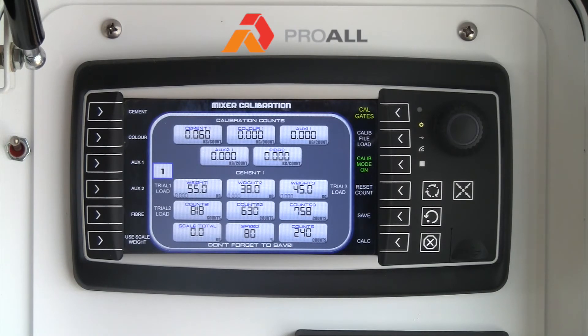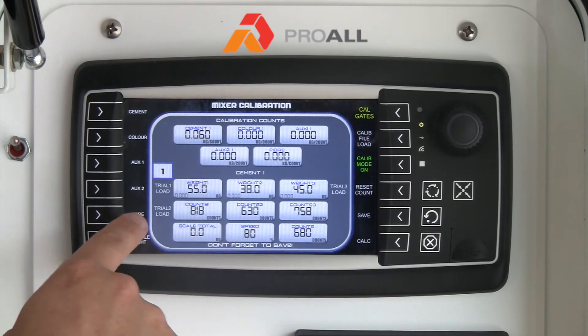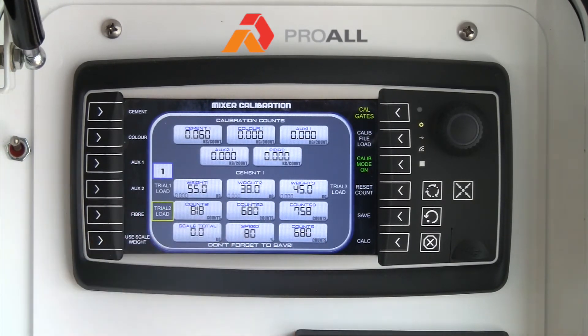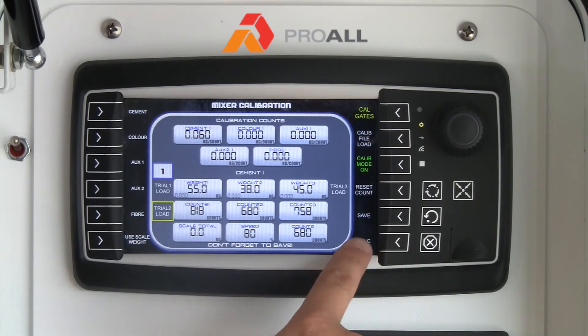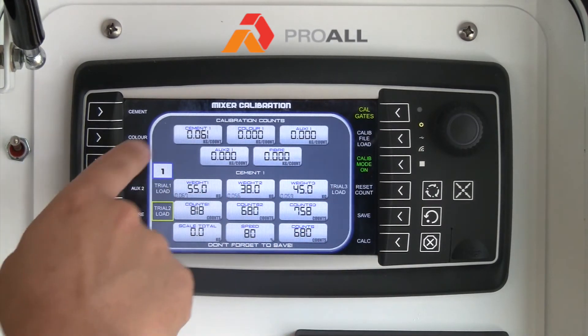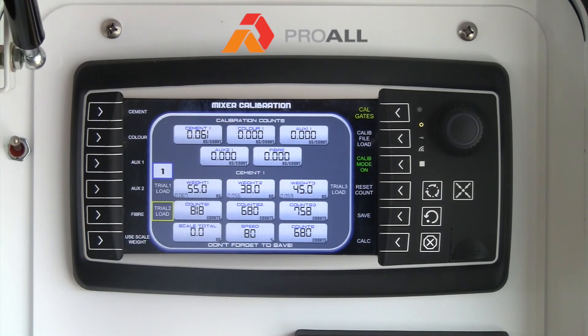Again we are going to get to around 680 counts and the process is exactly the same. Once you get there, you can hit Trial 2 Load and it will take the 680 and load it in. Once you have entered all three values and want to see your average cement calibration value, you hit the Calculate button and it takes the average of those three values and puts it into the cement box.